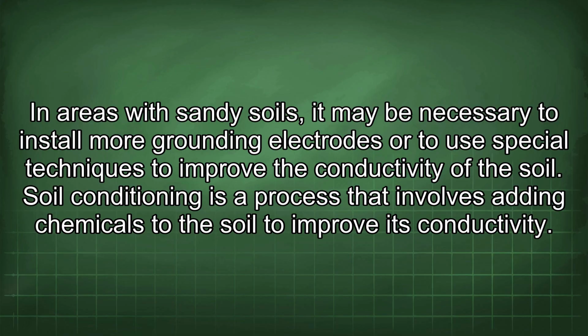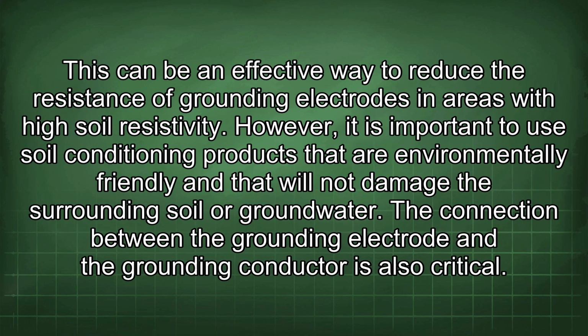Soil conditioning is a process that involves adding chemicals to the soil to improve its conductivity. This can be an effective way to reduce the resistance of grounding electrodes in areas with high soil resistivity. However, it is important to use soil conditioning products that are environmentally friendly and that will not damage the surrounding soil or groundwater. The connection between the grounding electrode and the grounding conductor is also critical.